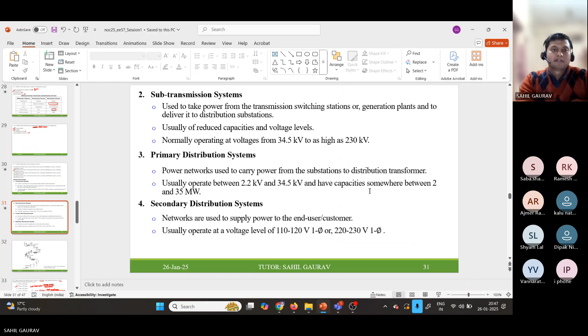So here you can see generation, transmission, then we have a substation, where switching happens, and then another substation, then the primary distribution network, and then the secondary distribution network. So this we call the distribution transformer. The transformer installed at the pole is the distribution transformer, and its rating is 400 volt for three phase, while 230 volt for single phase. Its output is the secondary side.